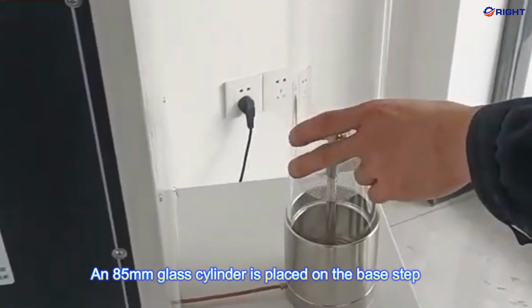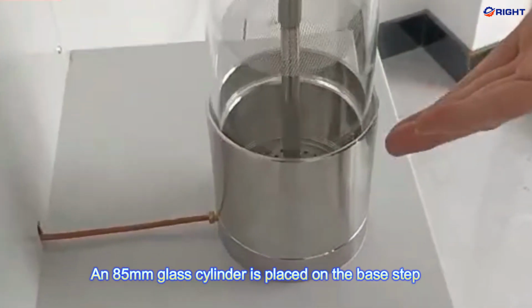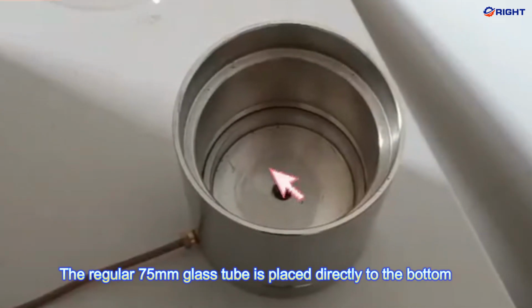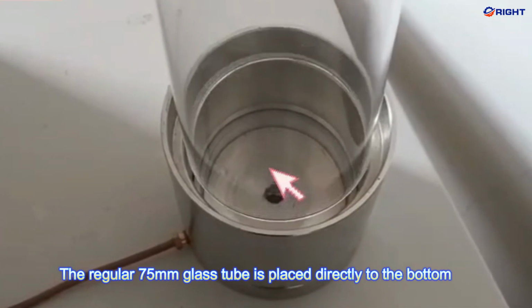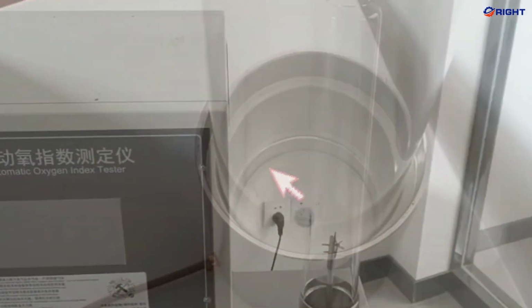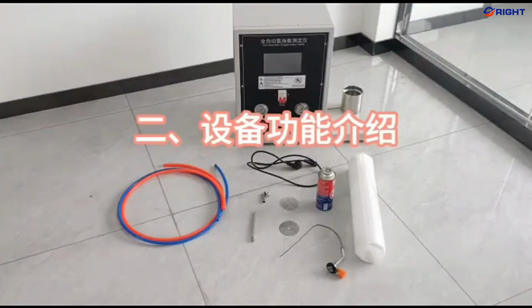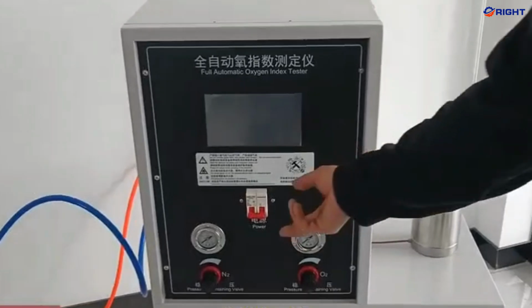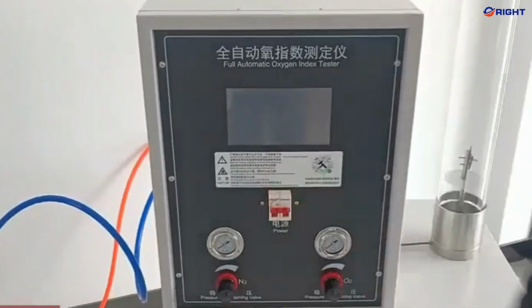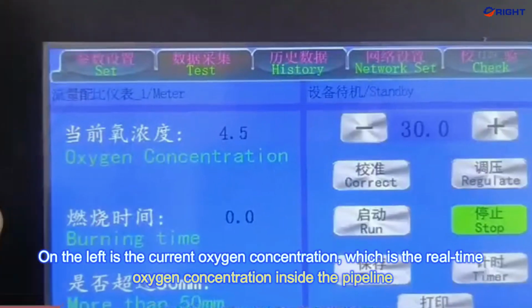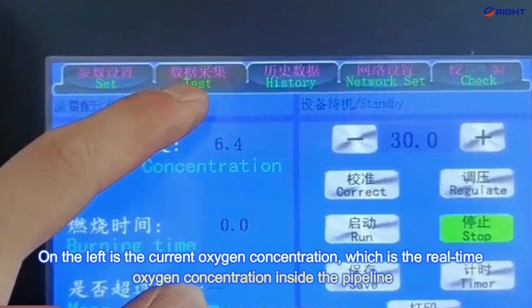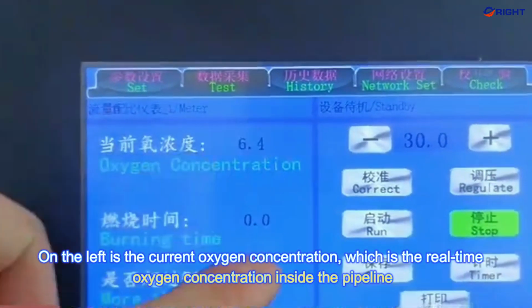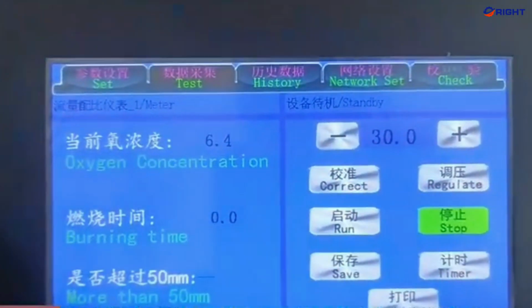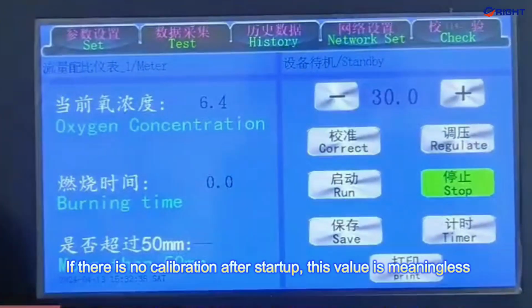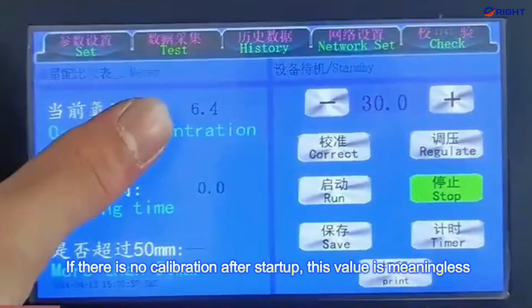An 85 mm glass cylinder is placed on the base step. The regular 75 mm glass tube is placed directly to the bottom. Power on. On the left is the current oxygen concentration, which is the real-time oxygen concentration inside the pipeline. If there is no calibration after startup, this value is meaningless.